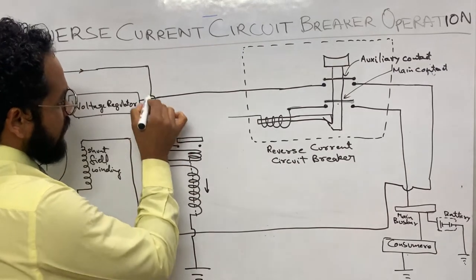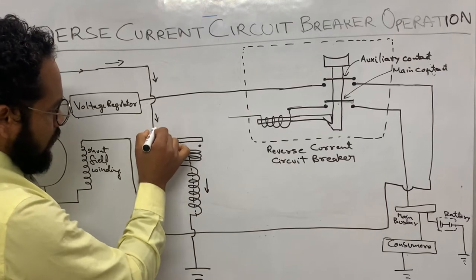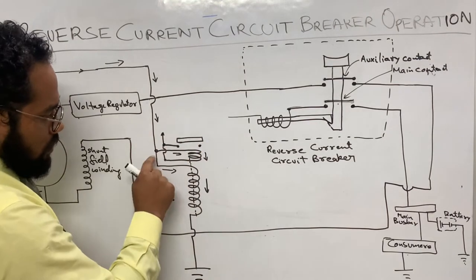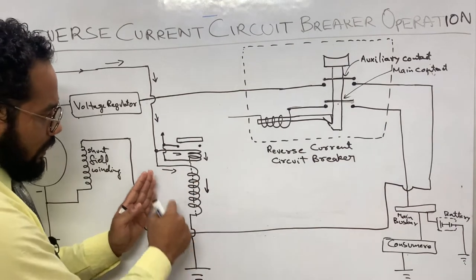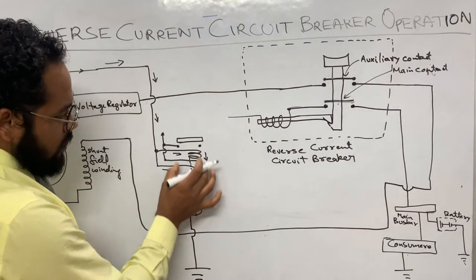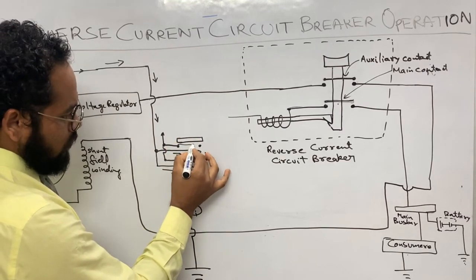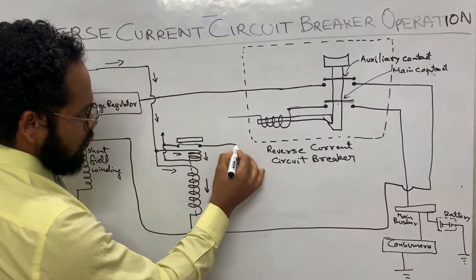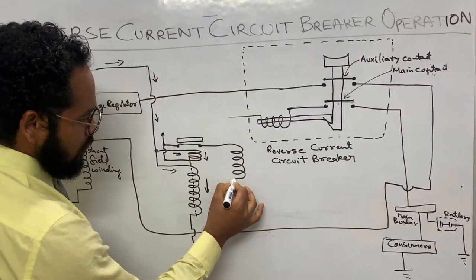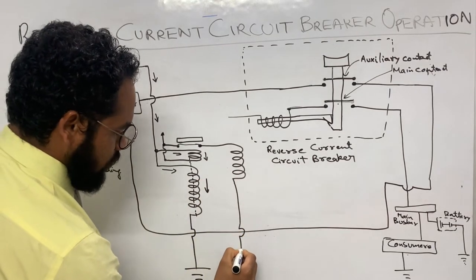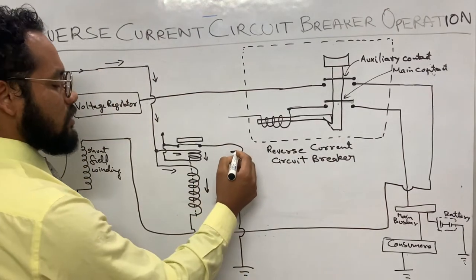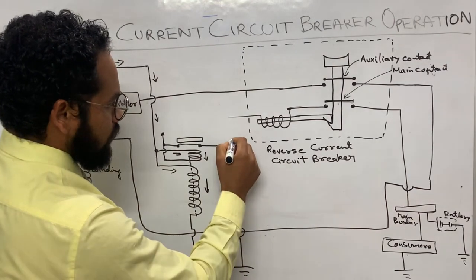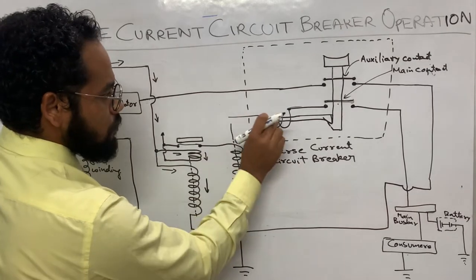Whatever current is coming from the generator goes to the voltage coil and also to the current coil. When the voltage coil is energized it will pull this contact down so the contact closes. This contact is connected to the coil of a line contactor, which is also grounded. So this coil belongs to the line contactor, and that line contactor has a contact here connected to the reverse current circuit breaker.